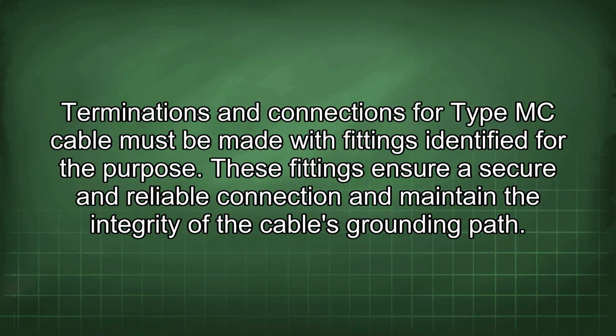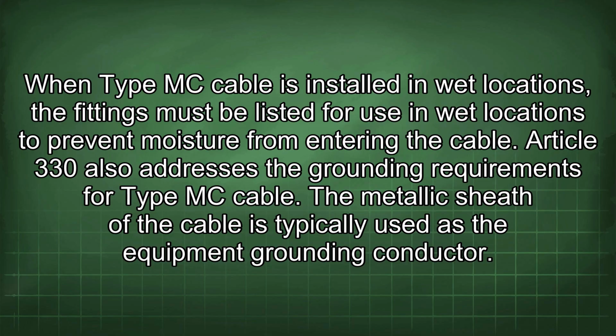Terminations and connections for Type MC cable must be made with fittings identified for the purpose. These fittings ensure a secure and reliable connection and maintain the integrity of the cable's grounding path. When Type MC cable is installed in wet locations, the fittings must be listed for use in wet locations to prevent moisture from entering the cable.